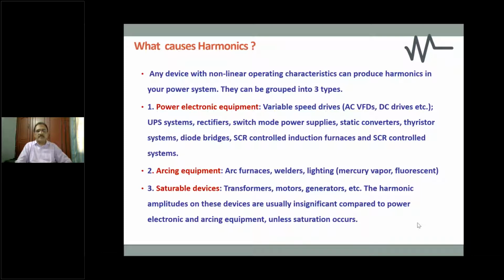Arcing equipments, for example, nowadays you find a lot of automotive industries or semiconductor industries coming up where they have this arc welding, TIG welding, MIG welding, and those are again equipments which will cause shape change, and that will be affecting the grid in terms of harmonics. And saturable devices, some of the transformers, motors, generators, they have also got their own contributions to the harmonic per se.